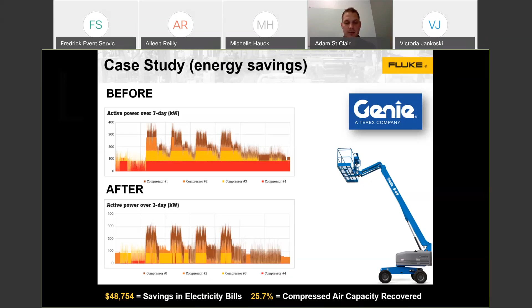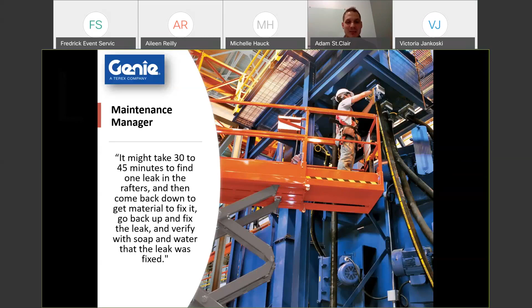One of their maintenance managers told us that they had previously used traditional ultrasonic leak methods, but it wasn't fast or efficient enough to have somebody dedicated to it full time. What used to take 30 to 45 minutes to find a leak with traditional soapy water methods could now be done in just seconds. So in addition to not buying a 5th compressor and saving $50,000 a year on energy, they also reduced the time spent finding leaks from 30-45 minutes per leak down to just a couple of seconds.